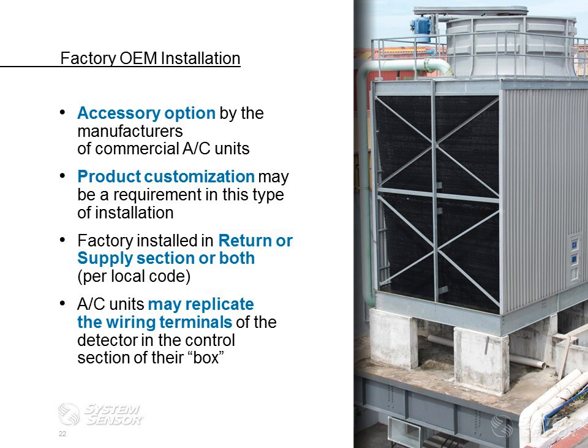And we also see the factory OEM installation, and we touched on that briefly, that most commercial rooftop manufacturers offer duct smoke detectors as a factory installed option. It's an accessory option for them. The product that is installed in those rooftop units a lot of times will require some customization to fit inside of their rooftop unit. They're factory installed, and it's usually optional where you have it installed. It can be in the return or the supply, or in both, depending on the local municipality and the size of the air handler unit.